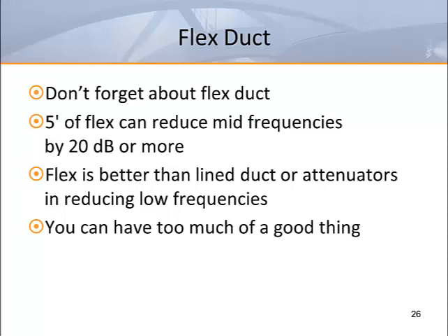Just because it comes in long pieces doesn't mean you have to use the whole thing. They do make tools for cutting flex duct, so there's no need to tie it up in a knot and shove it above the ceiling. Unfortunately, not all installing contractors are aware of these facts.